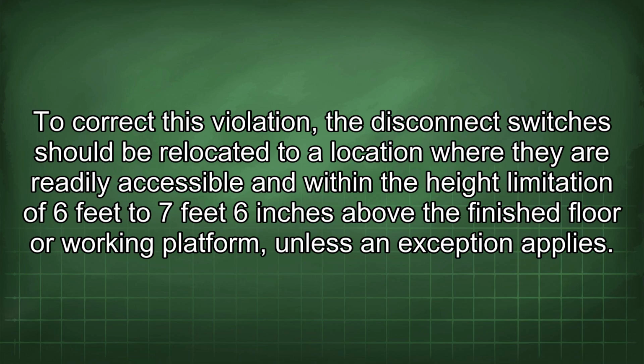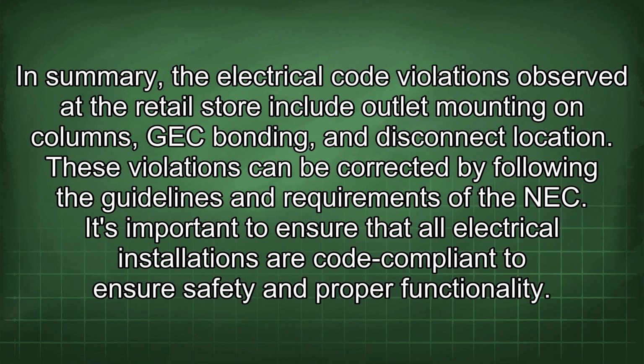To correct this violation, the disconnect switches should be relocated to a location where they are readily accessible and within the height limitation of 6 feet to 7 feet 6 inches above the finished floor or working platform, unless an exception applies. In summary, the electrical code violations observed at the retail store include outlet mounting on columns, GEC bonding, and disconnect location. These violations can be corrected by following the guidelines and requirements of the NEC.